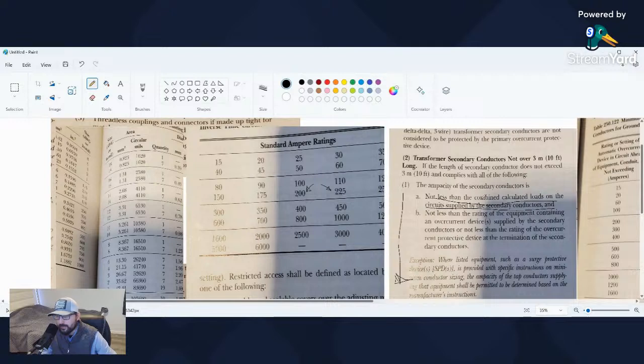That's the rating there, not less than the combined calculated loads on the circuits, and then not less than the rating of the equipment containing overcurrent devices. This is it here, supplied by the secondary conductors, or not less than rating of overcurrent protecting device at the termination of the secondary conductors. So this whole sentence here pretty much says that you cannot be less than the rating of the device your conductors are rated. So if you got a 200 amp breaker, you got to have at least 200 amps of wire. If you got a 400 amp breaker, you have to have 400 amps of wire.